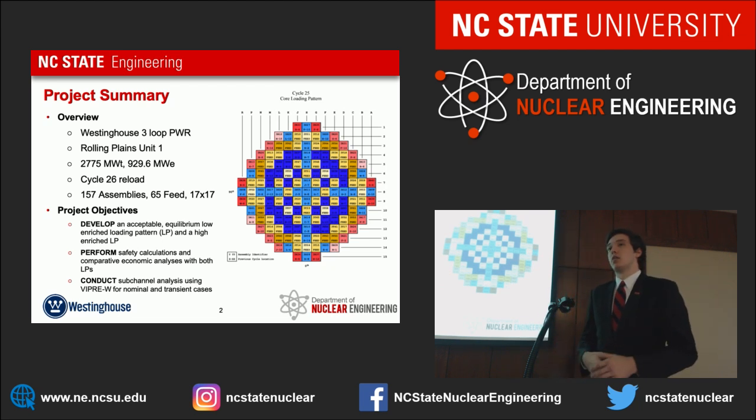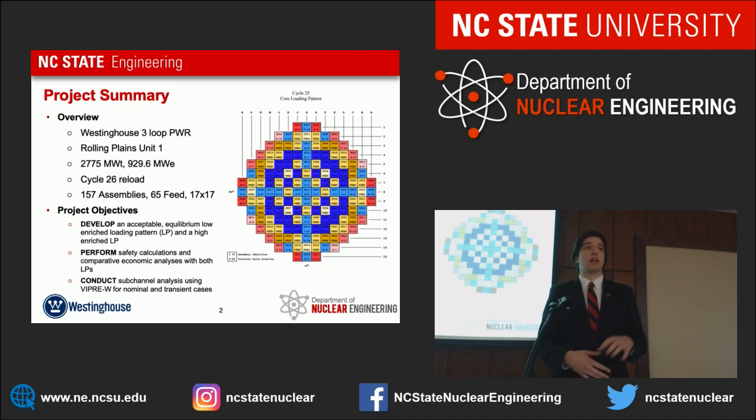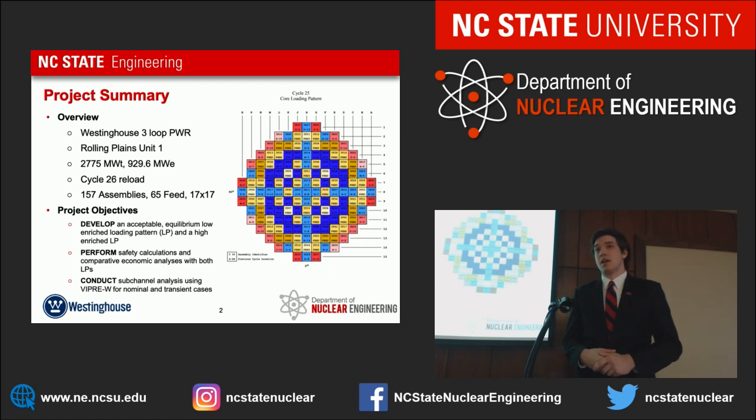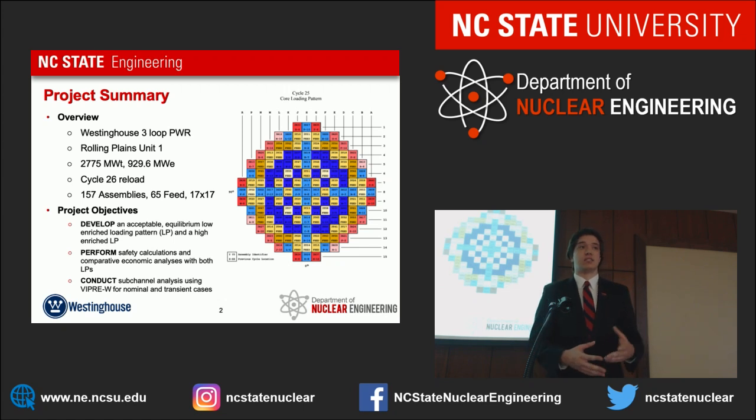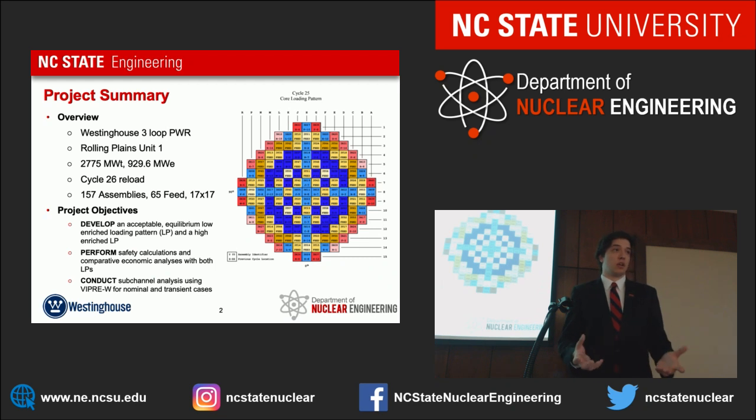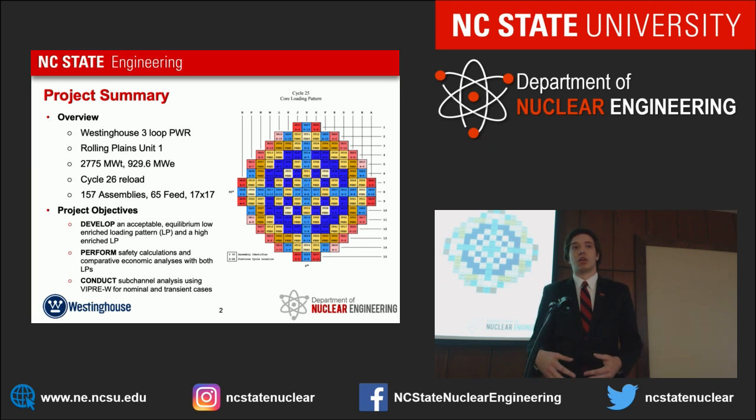In addition to that, our second goal was to create a high enriched loading pattern above the regulated 4.95% limit in order to compare the economics between the two. Of course, the safety analysis has to be done for these high enriched assemblies, and there are some more considerations that come with that increase in enrichment. Additionally, with our safety and operational constraints that are analyzed with our code, we added analysis for thermal hydraulics using Westinghouse's VIPRE-W code. This will be applied to all of our designs in order to ensure safety.